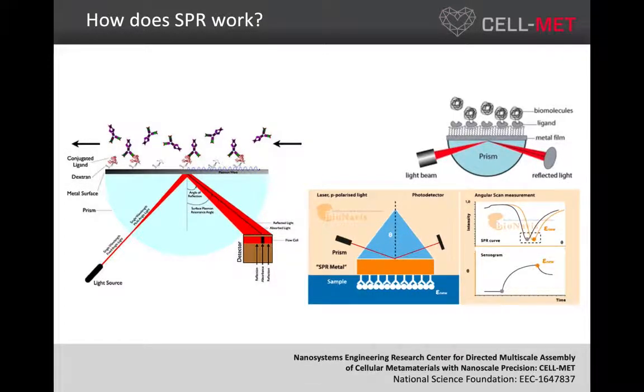Once the light is shone at the specific wavelength, it provides the crucial conditions for the light to have a total internal reflection within the SPR. And once that happens, and when the magnitude of the electromagnetic waves propagating on the surface equals the magnitude of the evanescent wave dissipating away from the surface in a vertical plane perpendicular to the surface of the chip, the resonance of surface plasmons occurs.